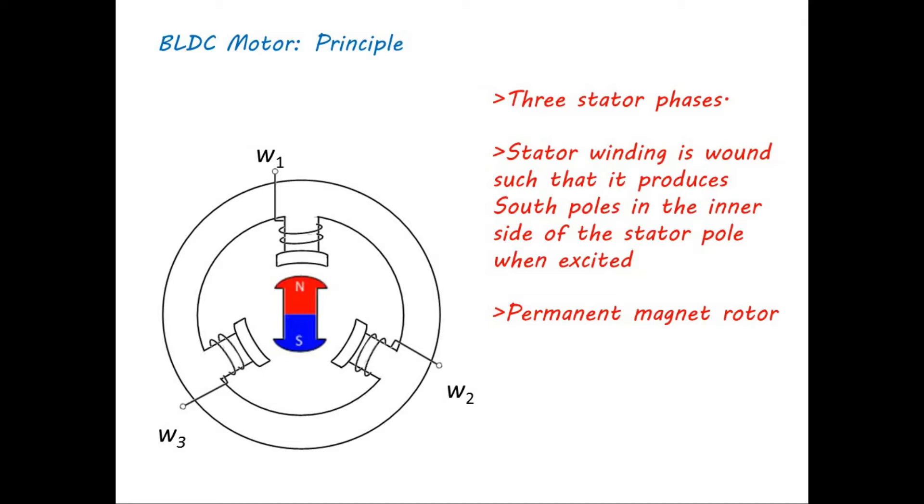From this rotor position shown here, if we excite the winding W2, south pole is created under W2 winding of the stator. The south pole of the stator attracts rotor north pole. At the same time, south pole of the stator repels rotor south pole. As a result of this, rotor rotates 120 degrees in the clockwise direction.